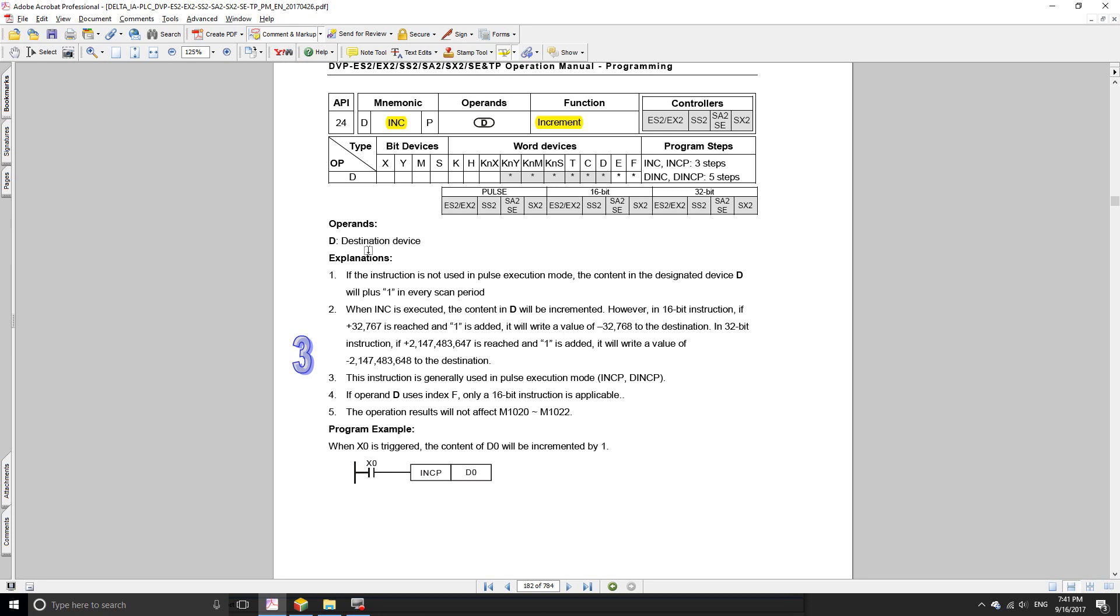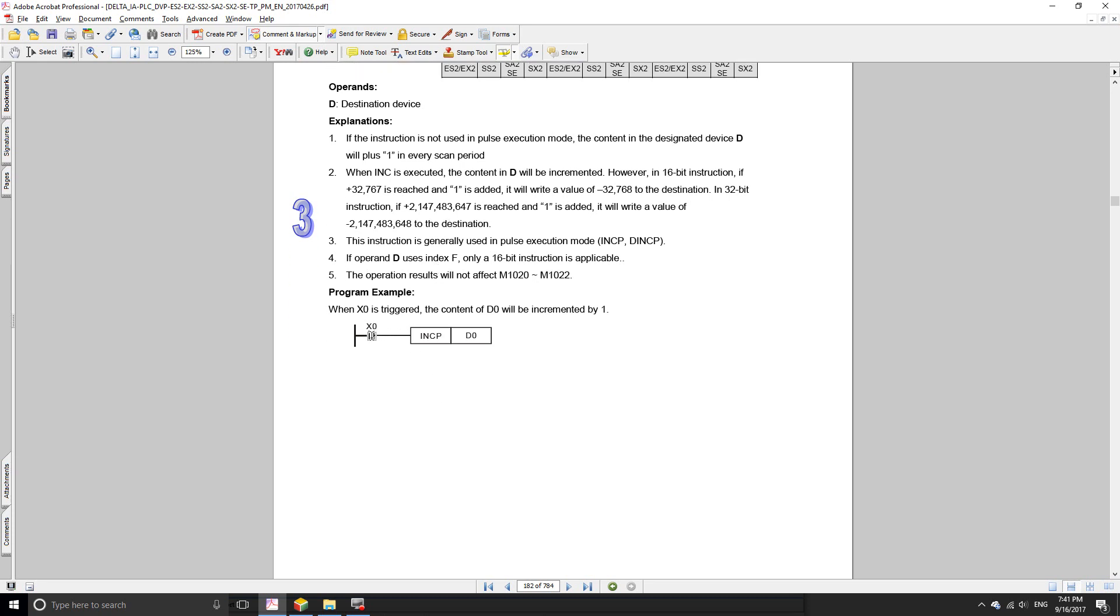The number by one. Something you need to be aware of is that whenever you execute this, for instance if you press X0 and use just the INC command alone, the value is going to increase for every scan cycle. So if you press the input X0 long enough for the PLC to go through, let's say 10 cycles, then D0 is going to increase by 10.